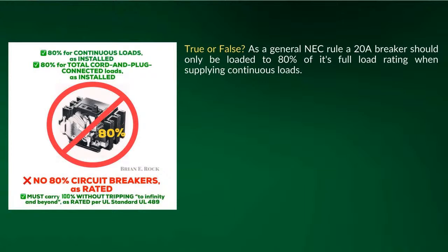So that's where this all comes in, and you can see that that's actually the triggering language in here for supplying continuous loads. Continuous loads is really confusing to a lot of people, because that means that appliance has to run continuously at full load for 3 hours or more. So look at a refrigerator. Is that a continuous load? Nope. Let's just say it runs for an hour, gets to its temperature, shuts off.